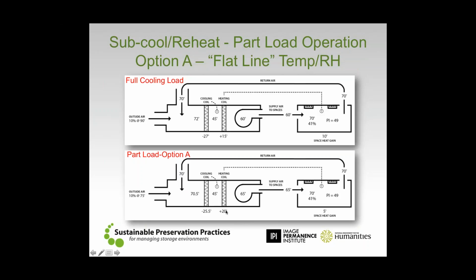We've just added 5 degrees worth of energy that our heating coil now has to do on a cooler day outside. I hope everybody's going, boy, that doesn't make any sense at all. You think about it, you realize, okay, well, why are we doing that? We're still trying to maintain that condition, but in order to do so, we have to send in warmer supply air. Well, to get that warmer supply air condition, this heating coil has to do more work, because the subcooling, the cooling coil, always does the same thing.